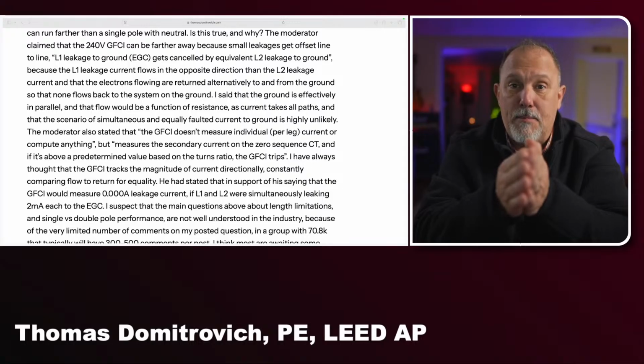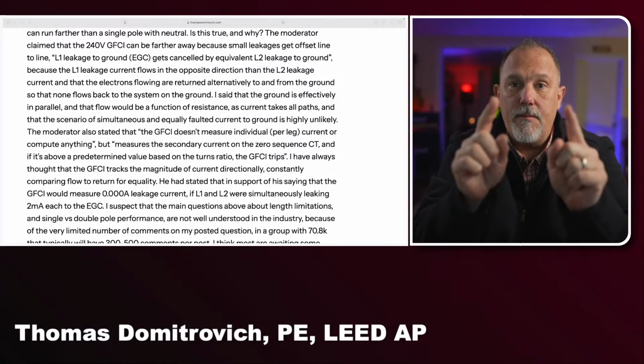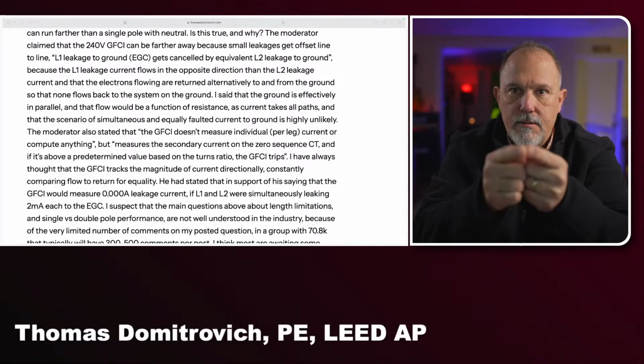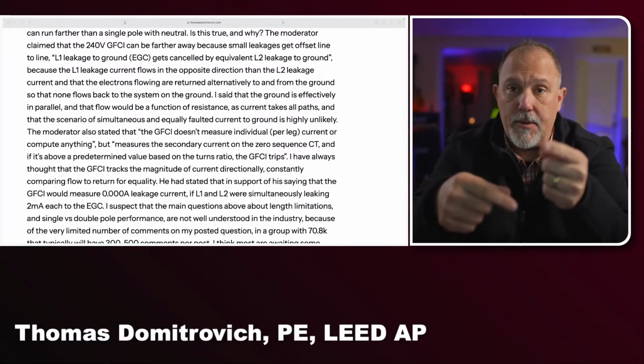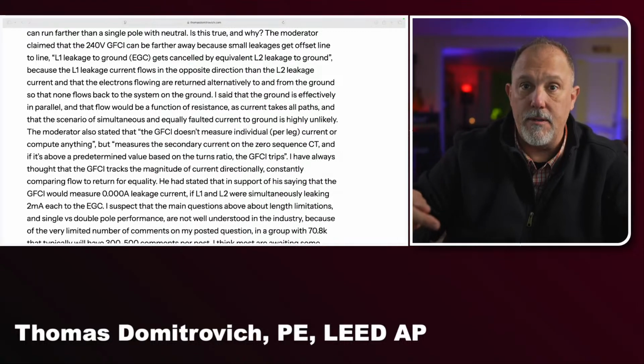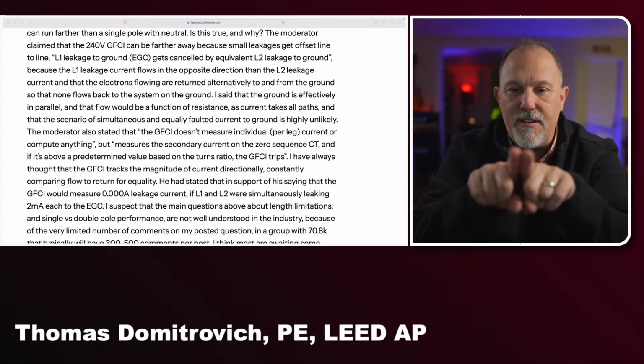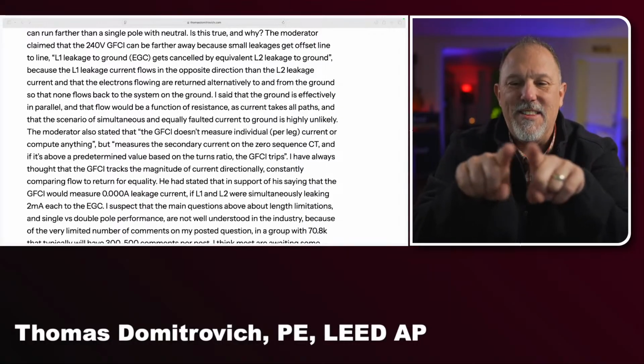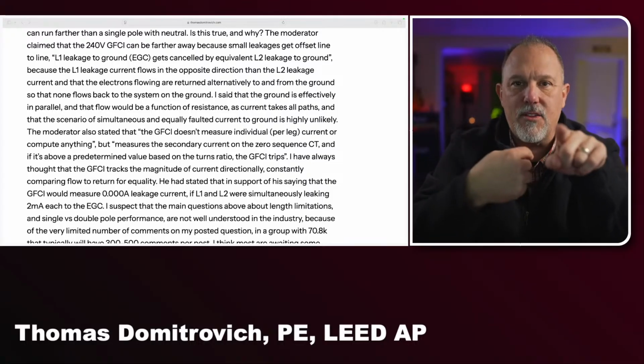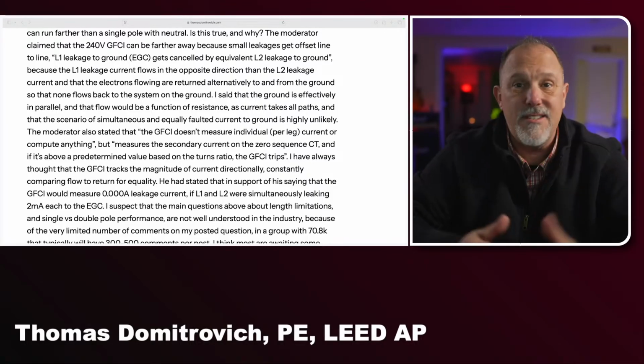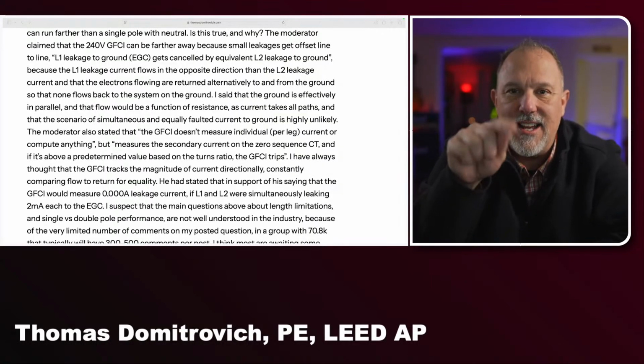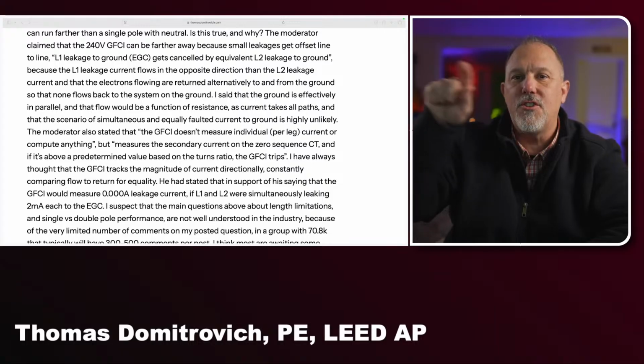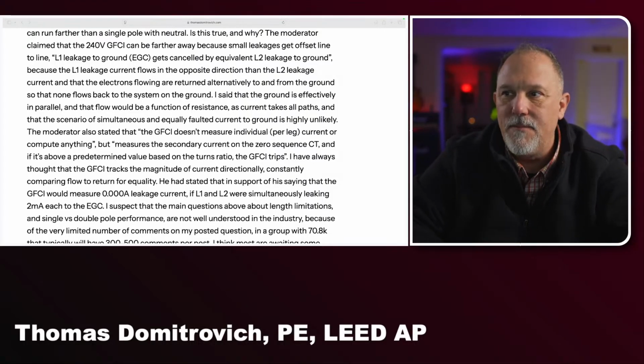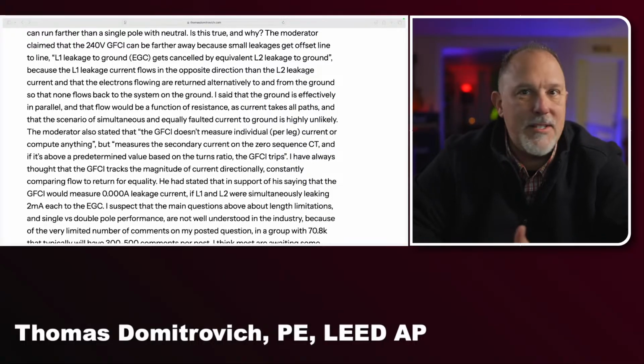Think about what has to happen to have leakage current going from the ungrounded conductors to the grounded conductor. Because if it goes outside the path, it's going to trip. If it goes over the equipment grounding conductor, it's going to trip. You would have to have the current going out the two blacks, coming back the white. If there's leakage between the two, they're still all in the path. If you touch that conductor and it goes to ground and it's greater than 4 to 6 milliamps, you're done. It's going to trip. If it's not greater than 4 to 6 milliamps, it's not going to trip.